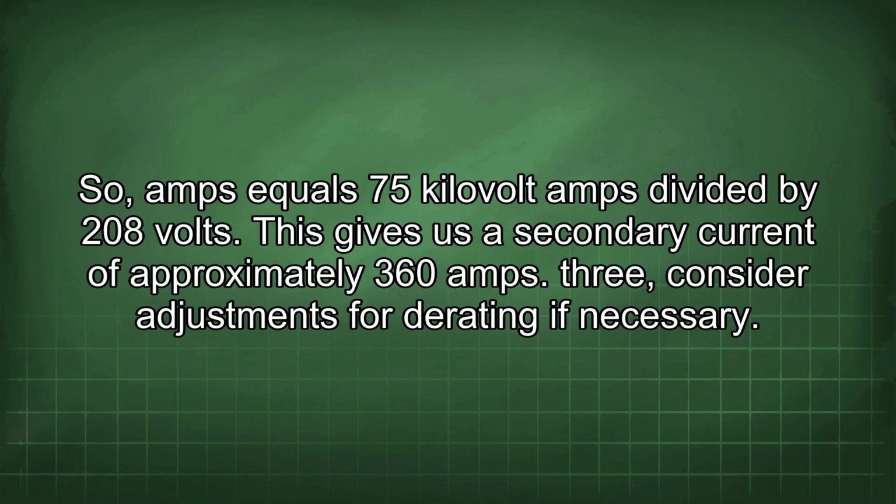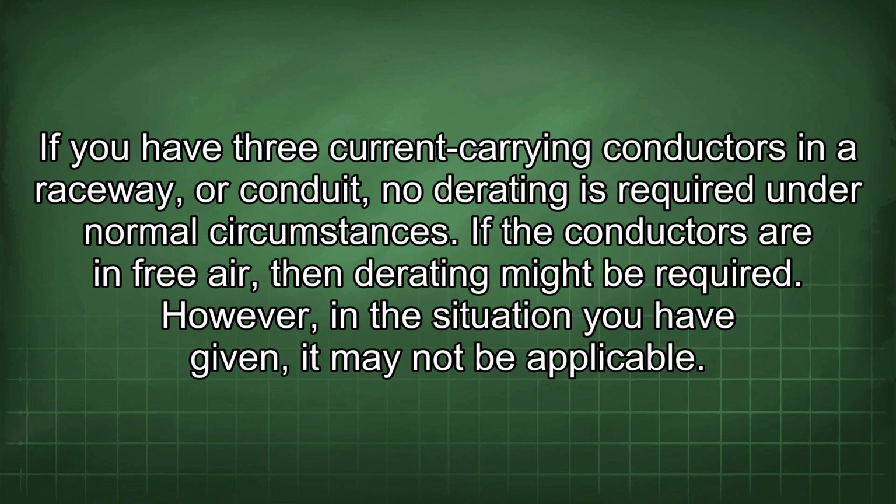3. Consider adjustments for derating if necessary. If you have 3 current-carrying conductors in a raceway or conduit, no derating is required under normal circumstances. If the conductors are in free air, then derating might be required. However, in the situation you have given, it may not be applicable.